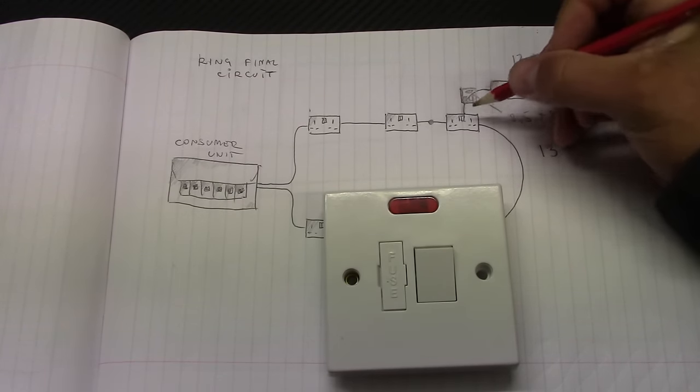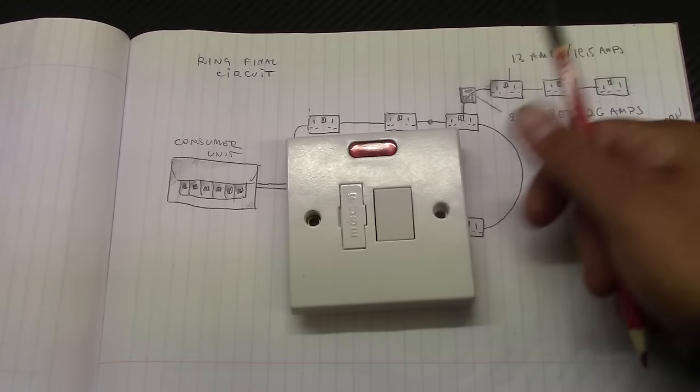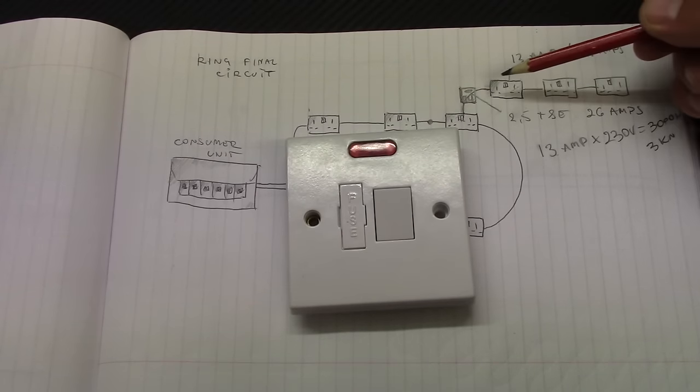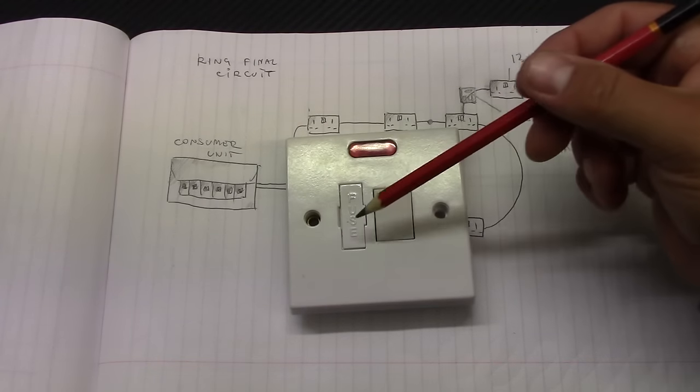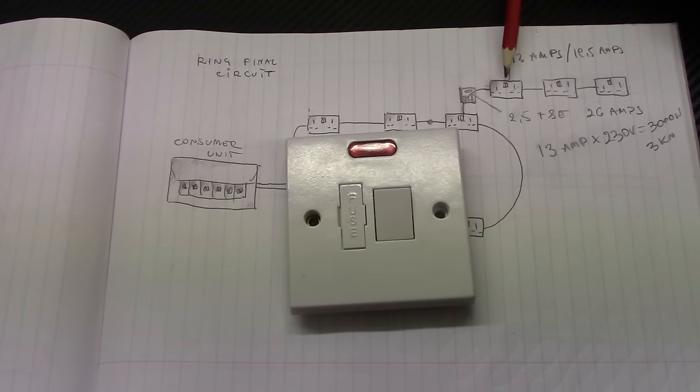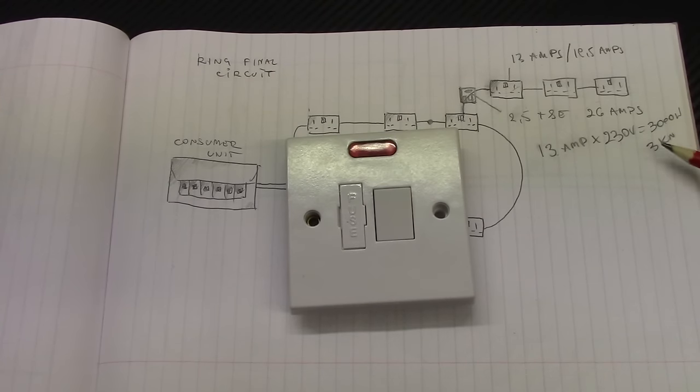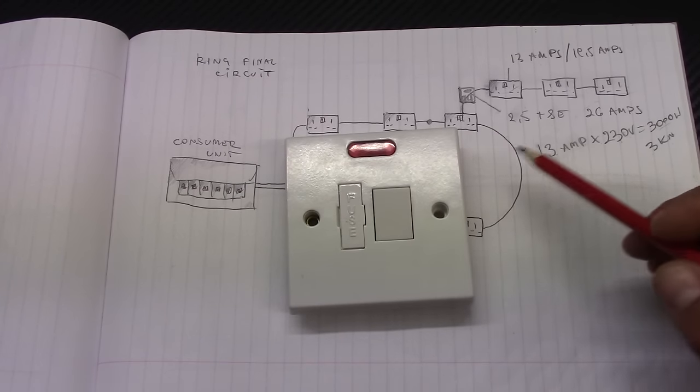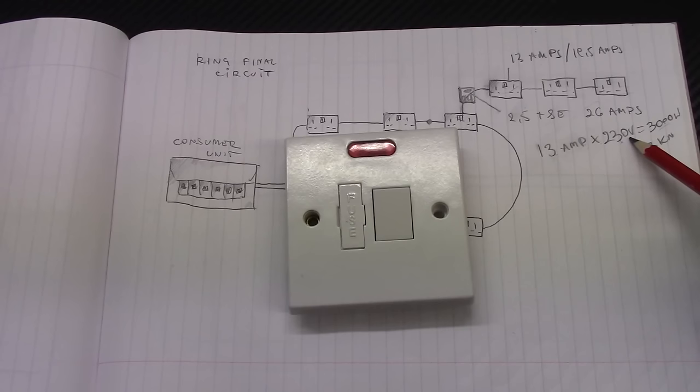This small device protects this cable. And the current drawn by all of the items plugged in these three sockets is limited to 13 amp fuse. So all the items, the power of the items is also limited to 3 kilowatts. So if you plug something which is more than 3 kilowatts obviously this fuse will be blown. 13 amp fuse by 230 volts gives us about 3000 watts.